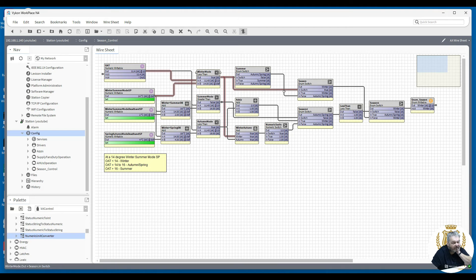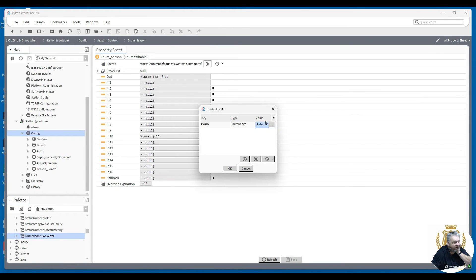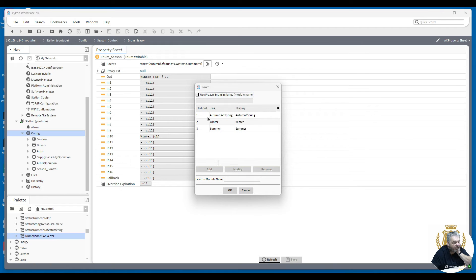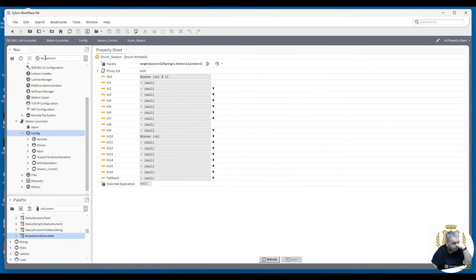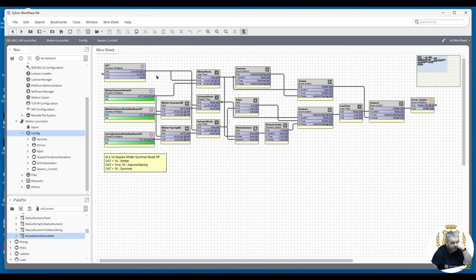We've got the true switch active because we're below 14 degrees, so that's saying winter mode. Let me show you the enum values: one is autumn and spring, two is winter, three is summer. So if you want to copy this, take a snapshot — summer mode, autumn mode, winter mode. We're in winter, which is true.